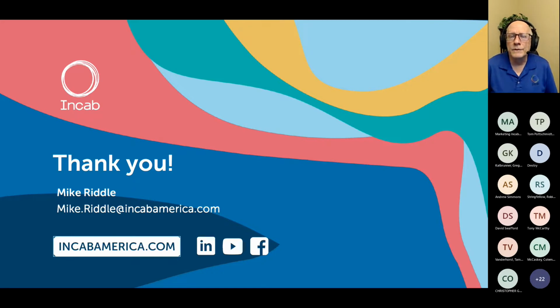So, for example, when you go do a fault current test at a laboratory, under lab conditions, air conditioned testing, a building on a not so hot day, a cable can cool down on the order of 30 minutes to an hour. But a long time ago, I did a fault current test at a testing center that had an outdoor span, and we were doing it in the summer, like I think it was July or August. I don't remember which. And that darn cable took nearly 4 hours before it cooled back.